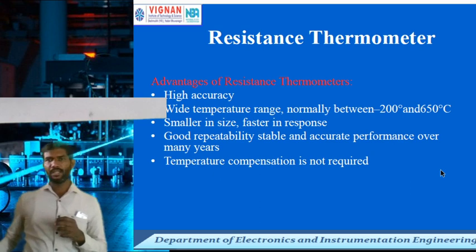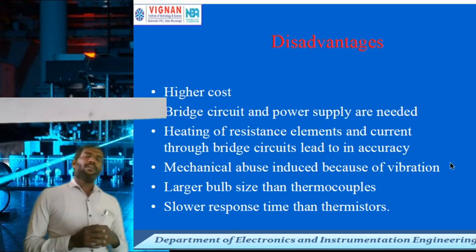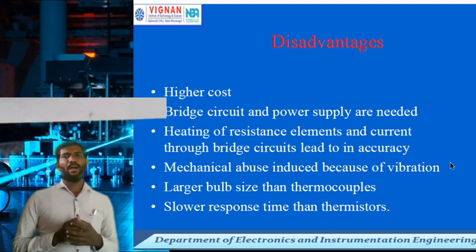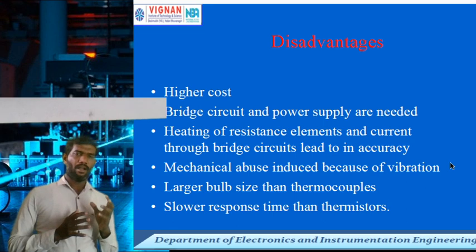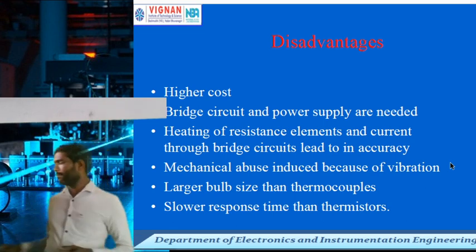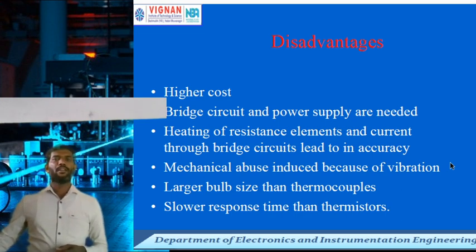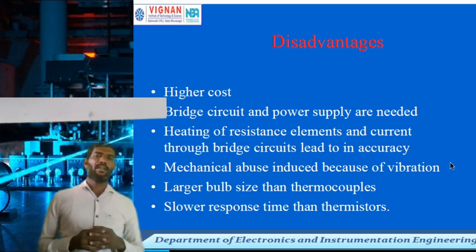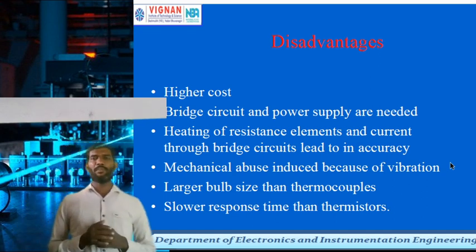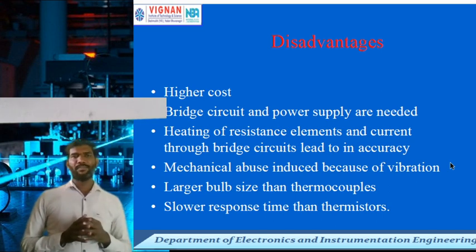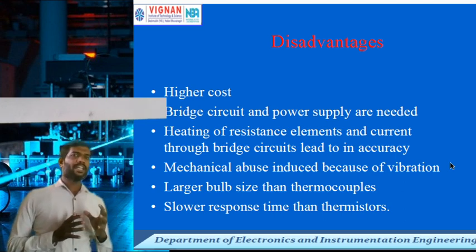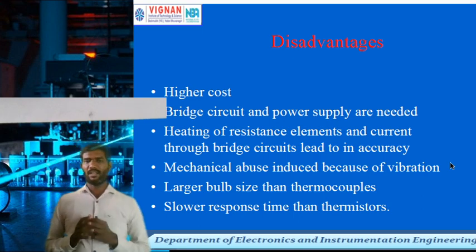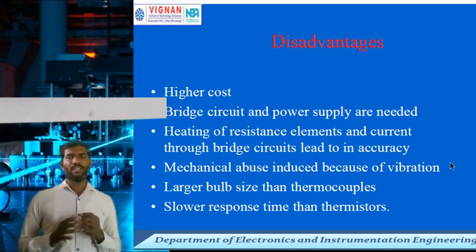Temperature compensation is not required for RTD. However, there are different disadvantages: the resistance thermometer has high cost, a bridge circuit is required, power supply is needed, heating of the resistance element and current through the bridge circuit leads to inaccuracy, mechanical abuse is induced because of vibrations, large bulb size compared to thermocouple, and slow response time compared to thermistor.